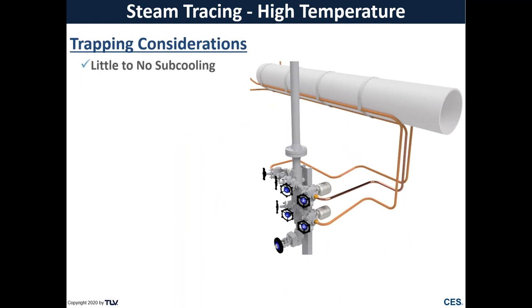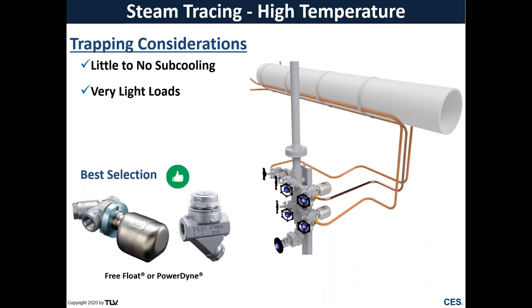So our considerations here, we want something with little to no subcooling. And again, we're going to have very small loads, usually less than 50 pounds an hour per tracing line. So the best selection here would be a free float or a thermodynamic type trap.